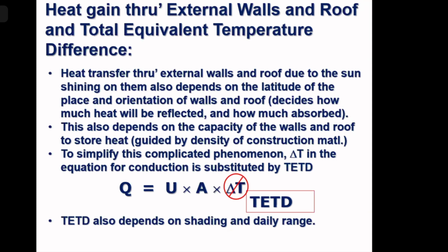Location means its latitude of the place. It depends upon the density of the building material. It depends on the color of the building material, dark color, light color, all given. Daily range of the location. So daily range you can find from the weather data in ISHRAE weather data, whatever I have given. Then in those pages there are other columns which gives daily range also. So you see the daily range and go by the daily range and find out TETD.